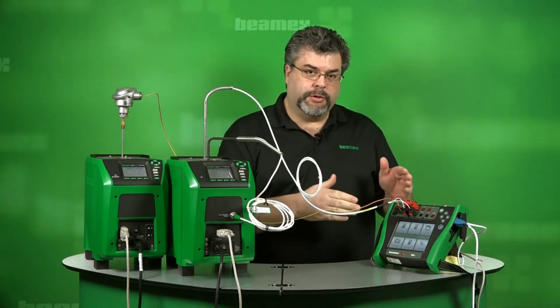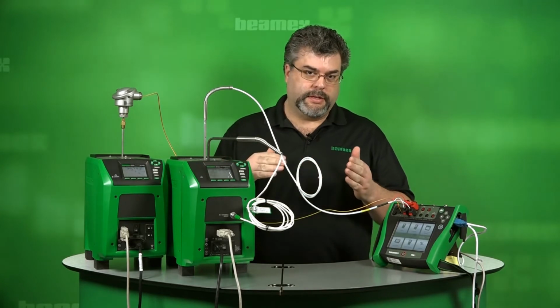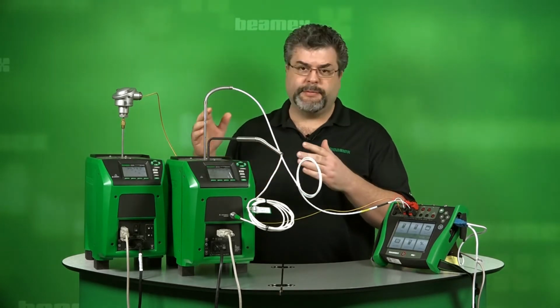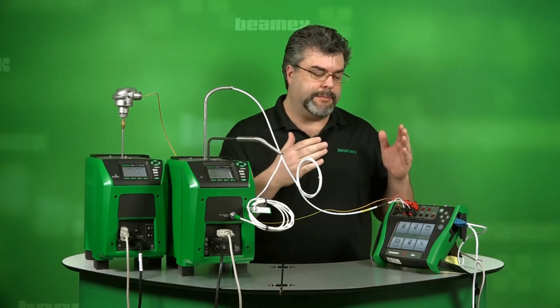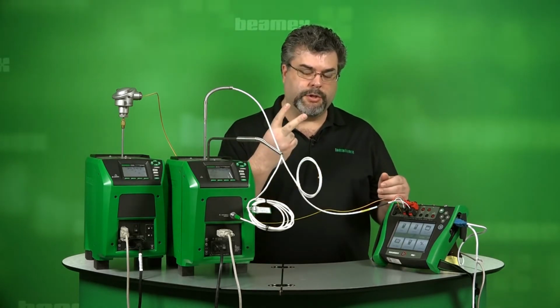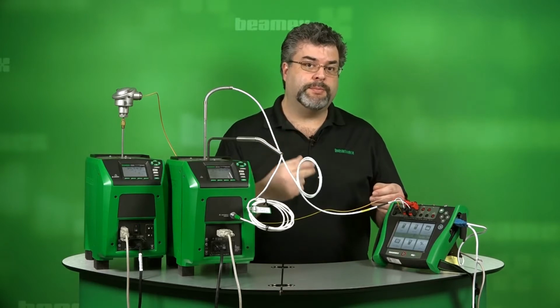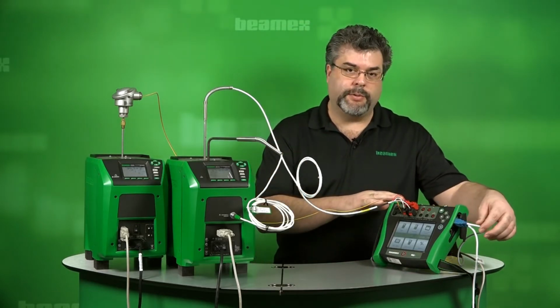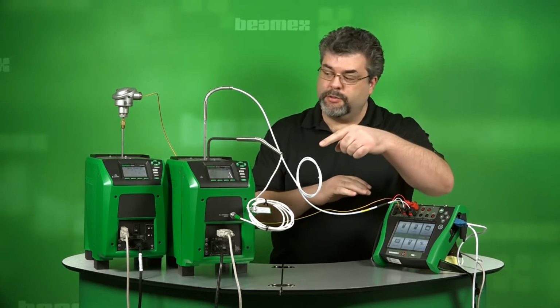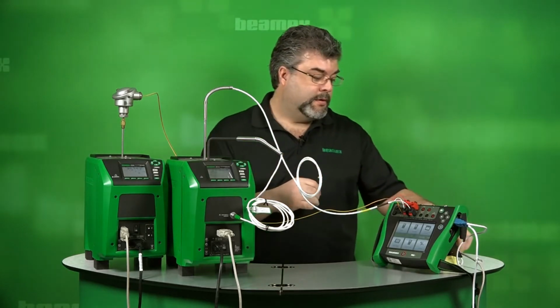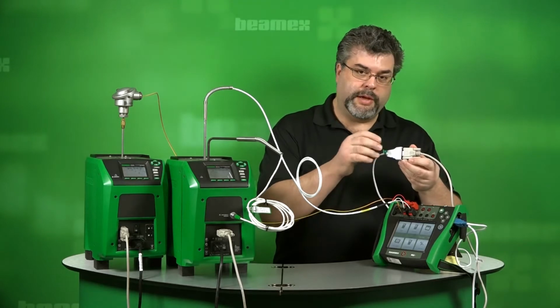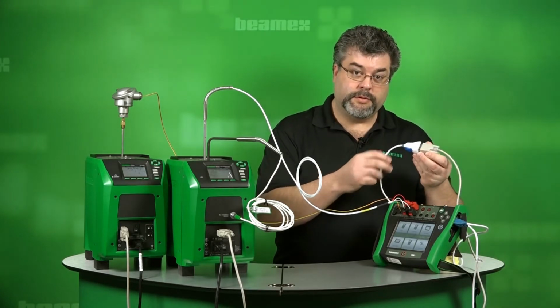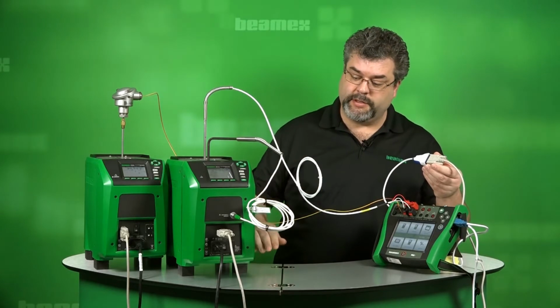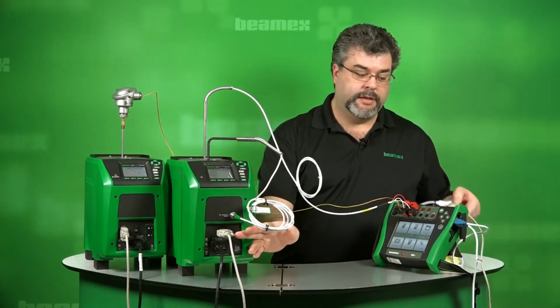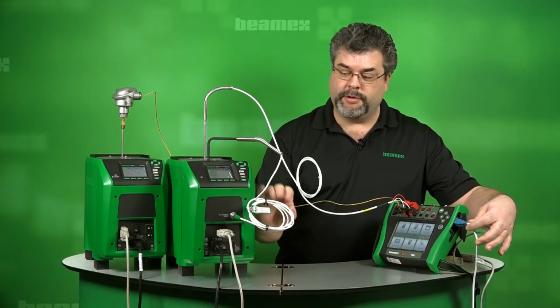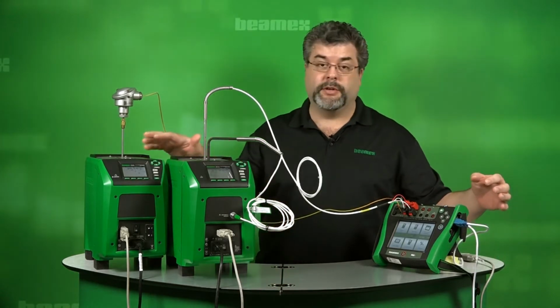The calibrator is controlling both of the dry blocks at the same time. You can actually test up to 4 different temperature sensors at the same time using this calibrator. We're using 2. And the way that we're talking is through a USB cable. On the side of the calibrator, we have a USB cable connected to each dry block. Here's what it looks like. So we have the USB converter to serial, which goes to the serial in the front of the dry block itself. So this first USB cable goes here, and the second USB cable goes over here.